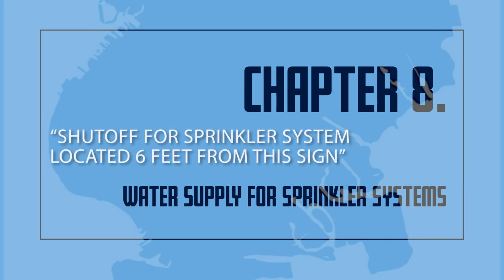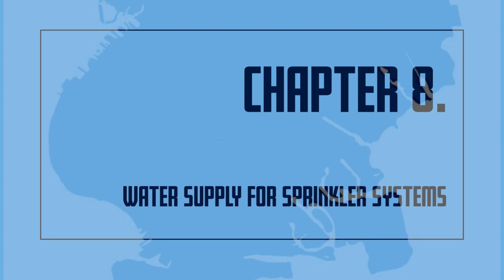When a sprinkler system is supplied from a public water main, the entire system shall be shut down by closing a non-indicating type control valve. This valve is located between the building and the water main in a box that is recessed into the sidewalk. The location of the box is found by reading a sign on the building or on a post nearby. The sign might read, "Shut off for sprinkler system located 6 feet from this sign," or it may have similar instructions. A special key will be required to operate this valve.